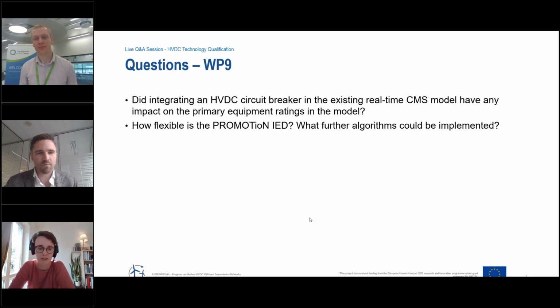Okay, this is one for you. Yes. So the PROMOTION IED, there's hardware involved, and currently the hardware is configured for sampling at 50 kilohertz. That means any algorithm that you would want to implement should be working in the range of 50 kilohertz. We've also tested at 20 kilohertz, and you could push it to 100 kilohertz. For anything above, at higher sampling frequencies, the hardware would need to be changed.